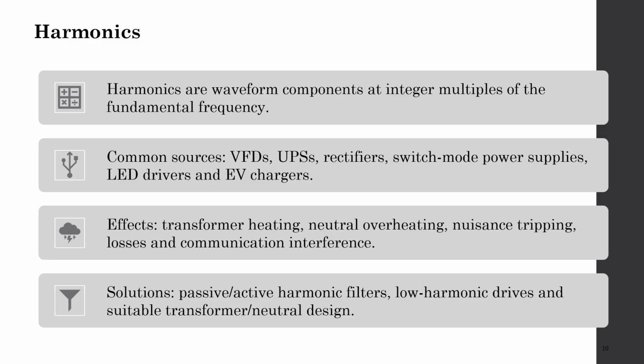This is an important one. Harmonics. Harmonics are waveform components at integer multiples of the fundamental frequency, namely third harmonic, fifth harmonic, seventh harmonic, ninth harmonic, like that. Common sources are VFD, UPS, rectifier, switch mode power supply, LED drivers, and EV chargers. This affects transformer heating, neutral overheating, nuisance tripping, losses, and communication interference. For the solution, we have to use passive and active harmonic filters, low harmonic drives, and suitable transformer and neutral design.